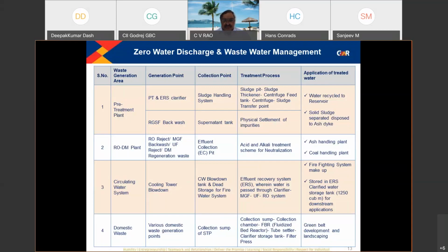And for the circulating system, from which we get the blow down water, we have an effluent recovery system, which was a challenge, because to control the four constituents in the system by dosing the lime as well as the dolomite at appropriate content to reduce the silica, and parallelly also to control the turbidity, because the increase of dolomite and lime in the system parallelly increases the turbidity to 5 to 6 over the inlet water. Again, to suppress this, we need to add the coagulant and flocculant in a balanced way.